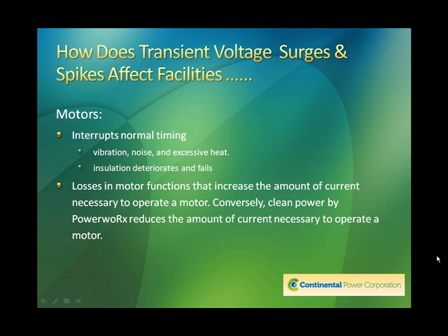Surges and spikes interrupt normal timing. It creates vibration and noise, and that creates excessive heat. Insulation of the windings deteriorates and then fails. Losses in motor functions increase the amount of current necessary to operate the motor.